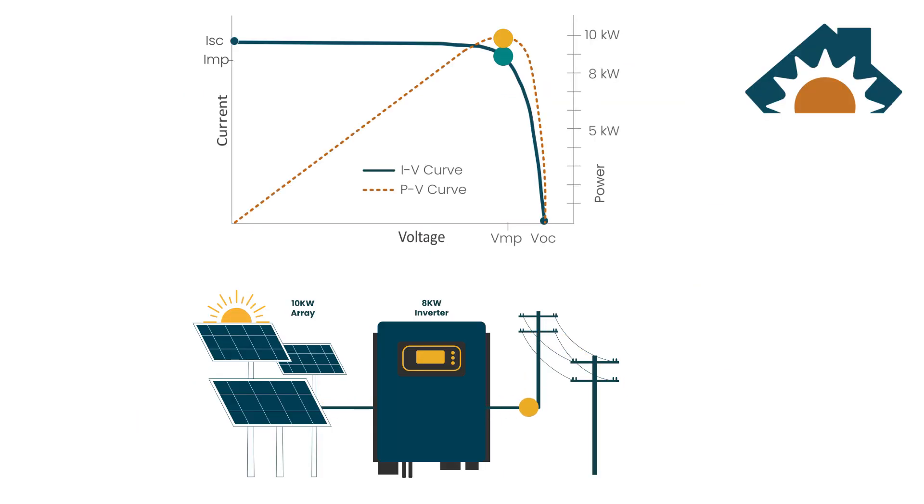So let's say you have a 10 kilowatt array on a bright, cold, sunny day connected to an inverter with MPPT capability. Well, the inverter will move away from the maximum power point voltage, noted as VMP, until the power matches the inverter output. Here you can see the inverter manipulating the voltage higher than the maximum power point until it reaches 8 kilowatts to match the inverter output.